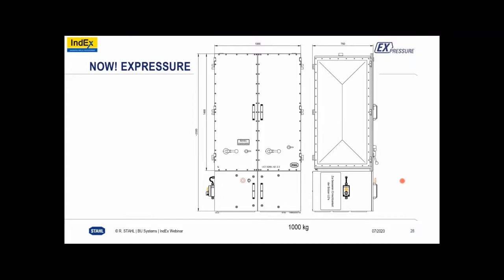So looking at this, I can definitely say that it's a higher quality solution, but it's also a safer solution. The reason is there is less chance for human-induced faults. Once this cabinet is placed in the correct location with the correct spacing from the rupture disc and from the sides, there is a low chance of a human-induced fault. Obviously you would want the hinge door type, but the Ex d flame paths are reduced compared to the other solution, where you had four different boxes. The more you open something, the more chance you have to induce a fault, to drop it, to scratch a flame path. This one only has one door. The other one had four. There's a much greater chance of the other one being modified, of a fault being induced, or of confusion. Here, you open up the doors and you look inside one enclosure.